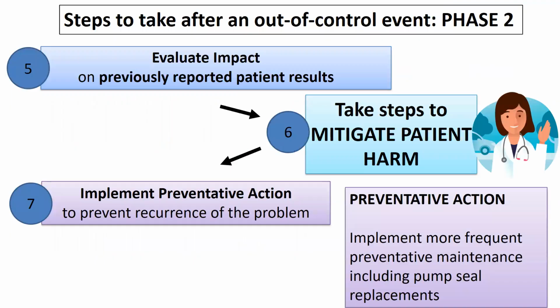The last step in our recovery process is to implement preventative action. The preventative action should seek to prevent the root cause of the problem. For example, the root cause of our glucose problem was a leaking pump seal. Therefore, the lab would want to implement more frequent preventative maintenance activities that include pump seal replacements to prevent recurrence of this problem.